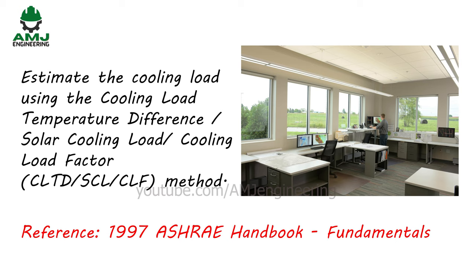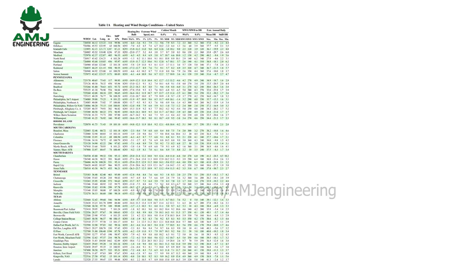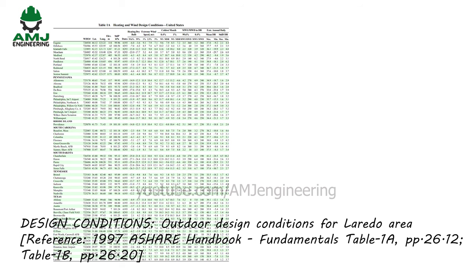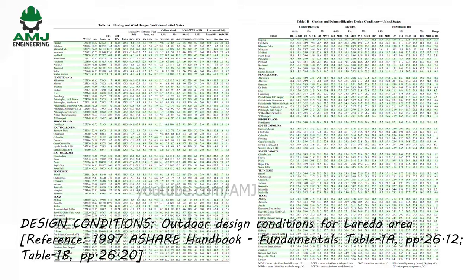We will use the cooling load temperature difference, solar cooling load, cooling load factor method — known as the CLTD-SCL-CLF method. The reference for this hand calculation method is the 1997 ASHRAE Handbook of Fundamentals. Unless otherwise noted, all tables seen through this lecture are taken from that book. The outdoor design conditions for Laredo are found in Table 1A, Chapter 26, Page 12, and Table 1B, Chapter 26, Page 20.